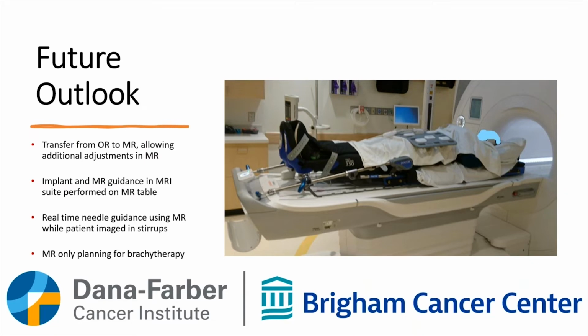What these stirrups and this system give us the capability of doing is, knowing that we can't have an ultrasound in our MRI room, we can further expand trying to use our MRI for real-time guidance. So instead of using the ultrasound for the initial implant, we can further research how we can use a live MRI to guide the needles. So that's something that this allows us to do. It also allows us to not transfer the patient in between, say, an OR, a CT, and an MRI, but to keep them in that same position throughout the MRI.